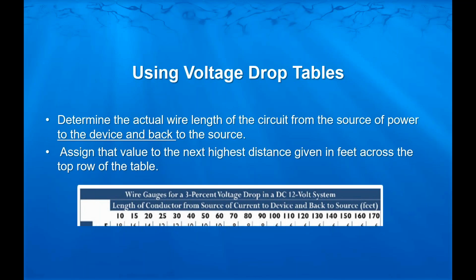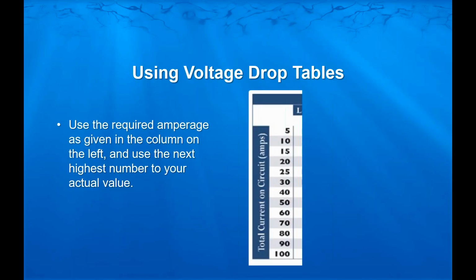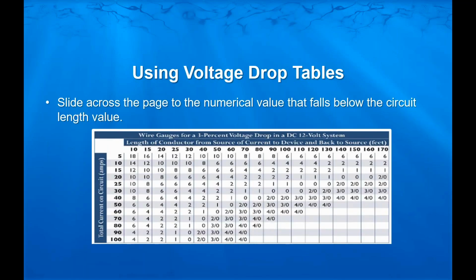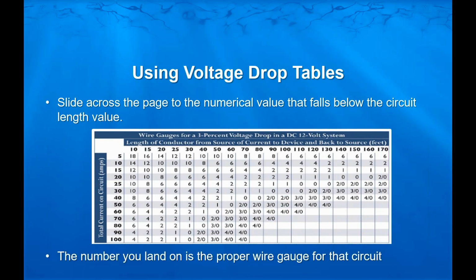Assign that value to the next highest distance given in feet across the top of the row of the table, if it doesn't match one exactly or very closely, within 1 foot. So use the amperage that you need to deal with, which is given on the left-hand side of the column. And then again, use the next highest number to your actual value if you're in between numbers. So you want to slide across the page from your amperage number across to below your distance number.